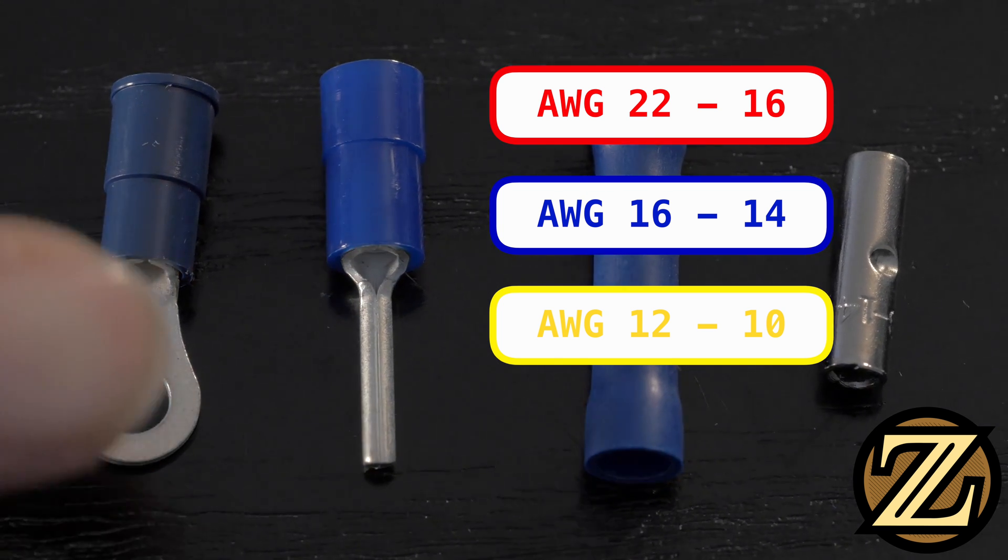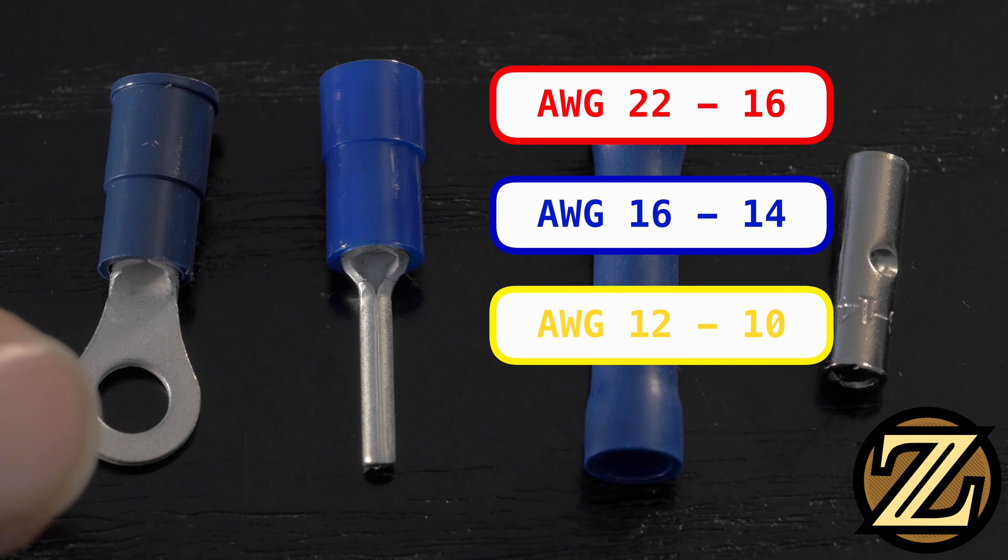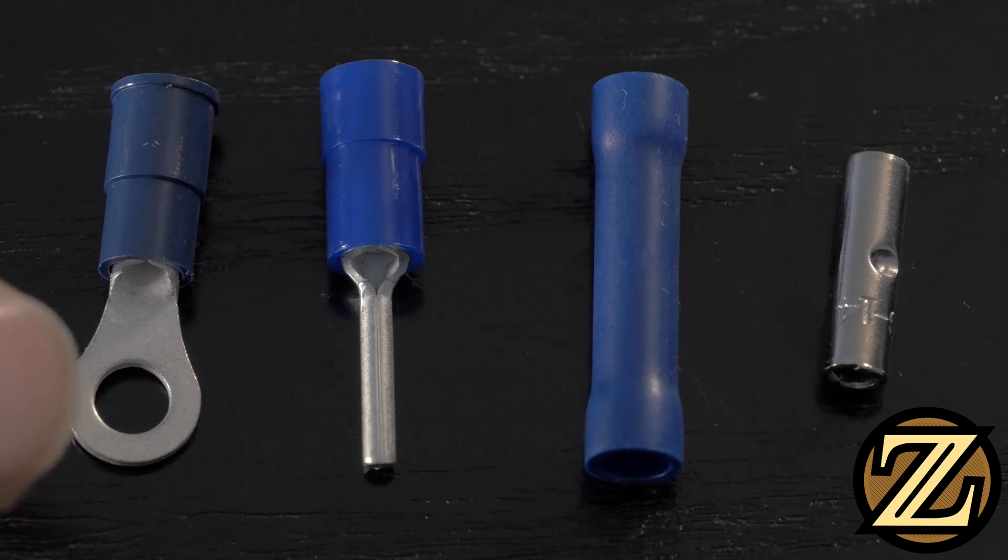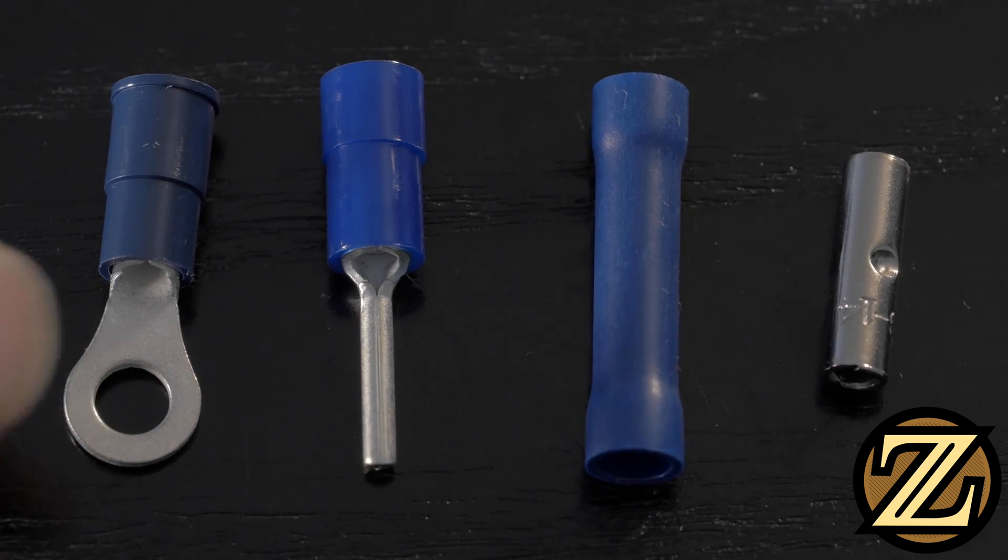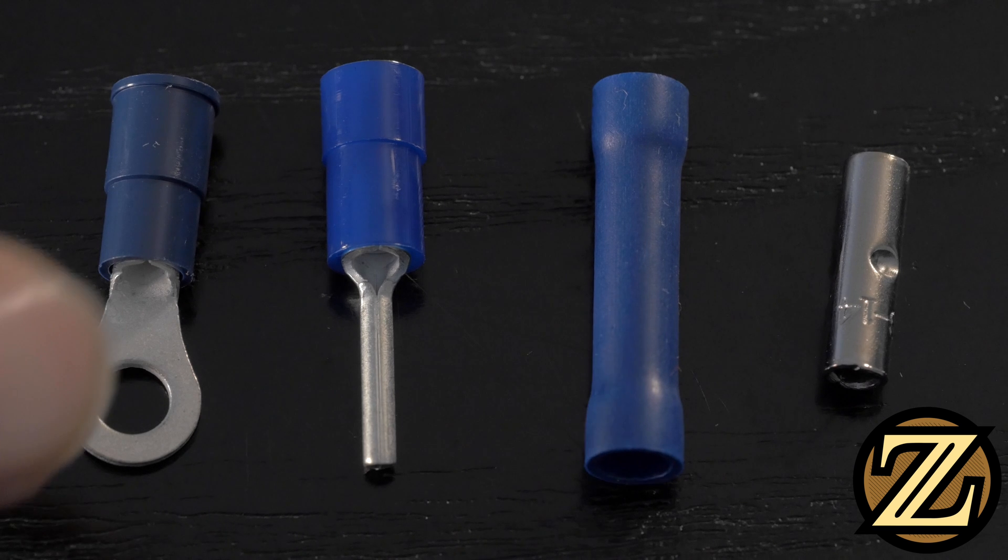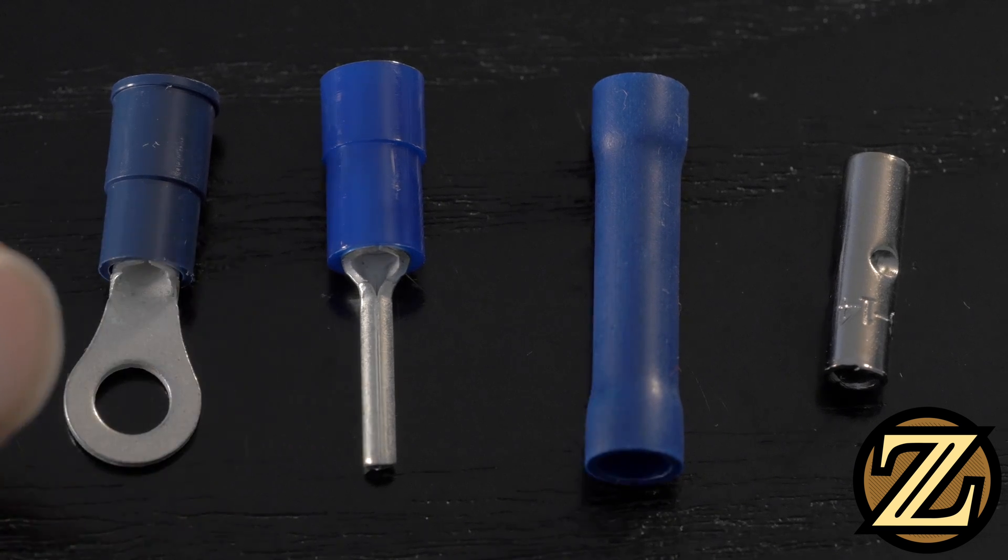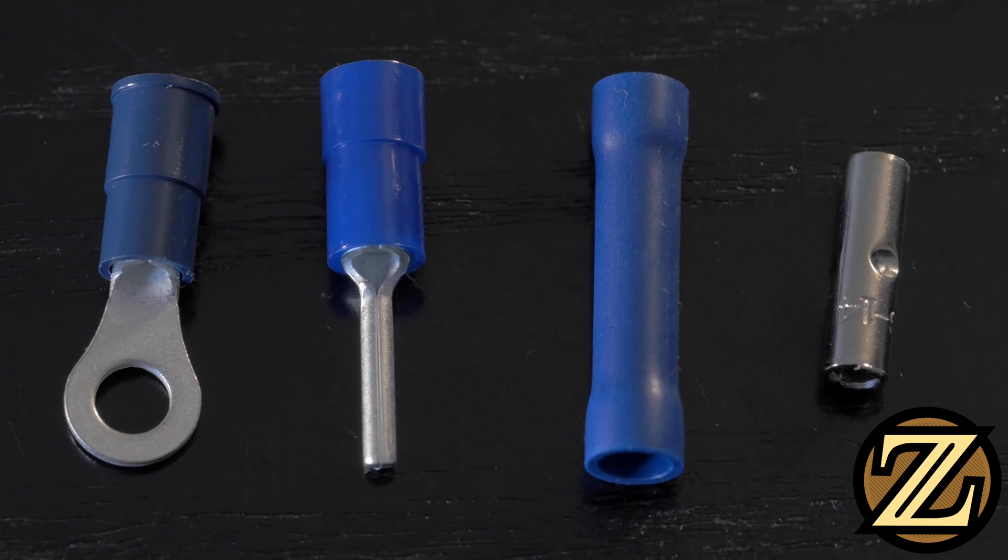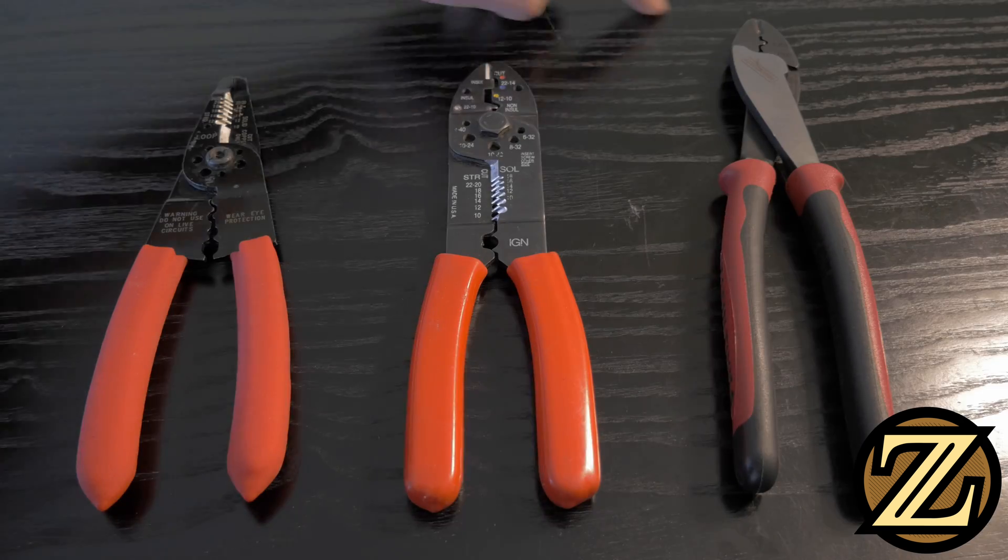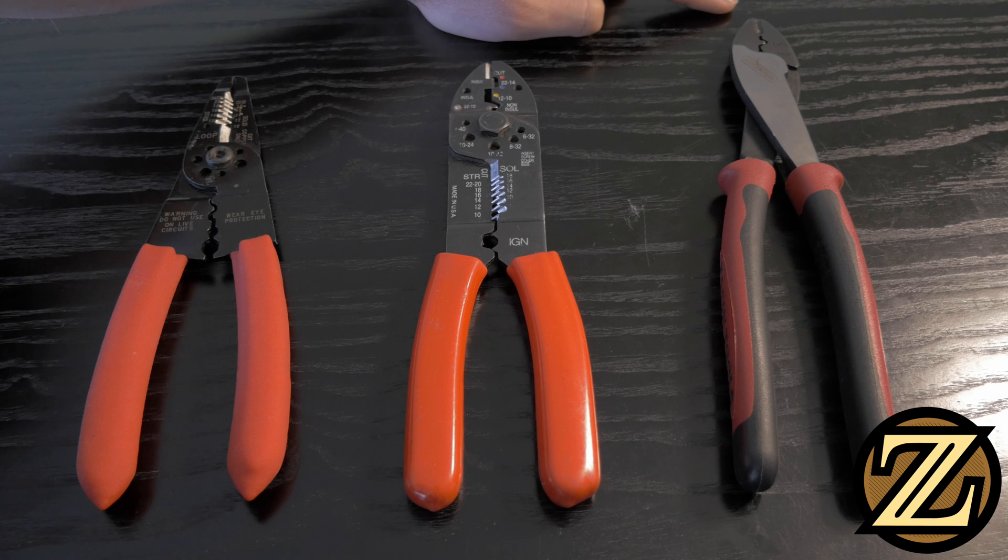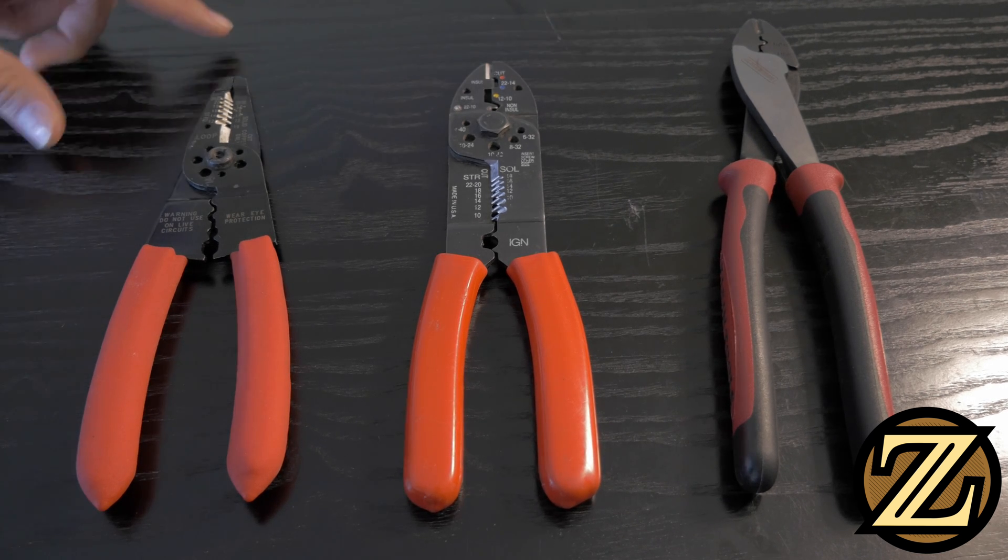Make sure you have the right size terminal for the wire that you're working with, and also make sure you have the right kind of wire for the terminal that you're going to be applying to it. All of these are designed for copper only wire, so you need to make sure that you're using copper wire to make sure you get a good crimp. Here I have three different crimping tools. The best tool is the one that offers the greatest amount of leverage so you can get the highest amount of crimping pressure.